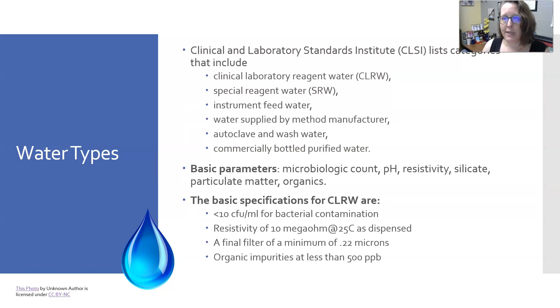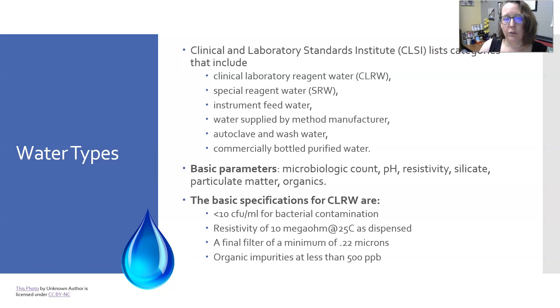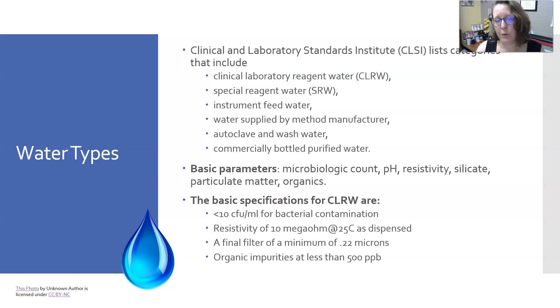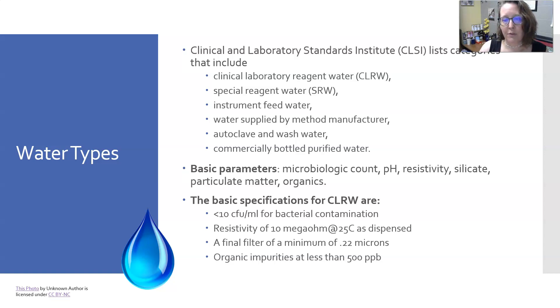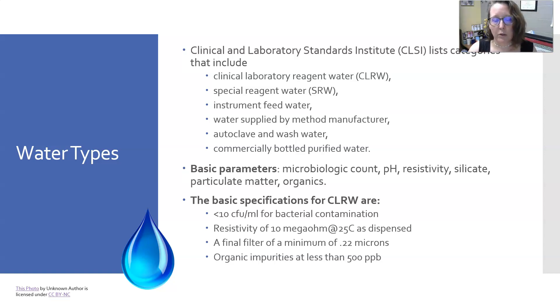CLSI — the Clinical and Laboratory Standards Institute — lists categories for water, including clinical laboratory reagent water (CLRW), special reagent water (SRW), instrument feed water, water supplied by the method manufacturer, autoclave and wash water, and commercially bottled purified water.